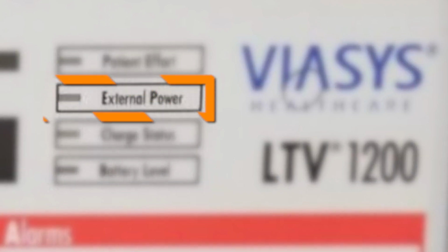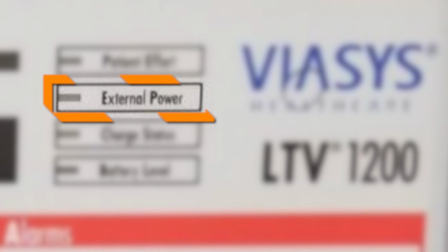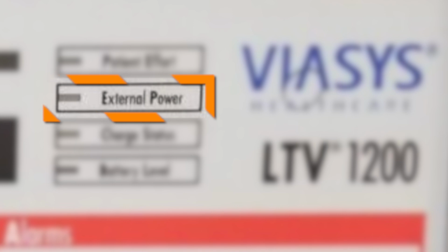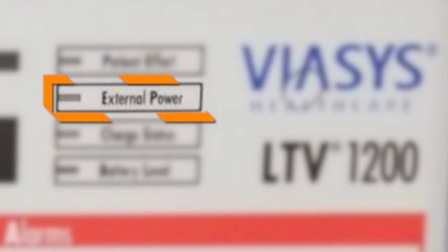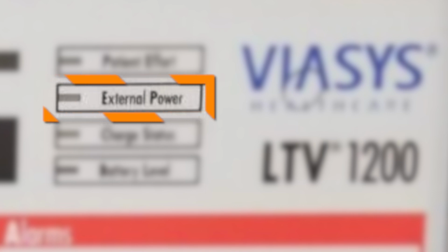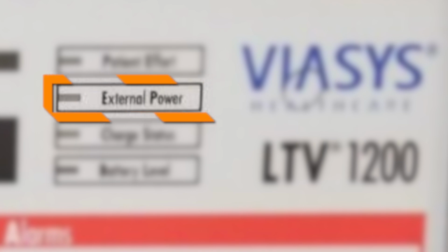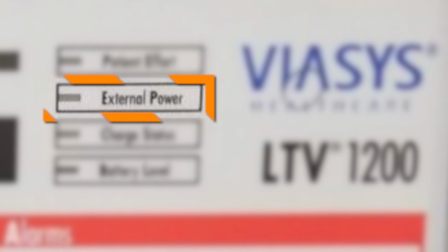The external power indicator shows the level of external power while the ventilator is operating from an external power source. When the ventilator is running from the internal battery, the external power indicator is off. When running from external power, the indicator shows the following levels. Green means the external power is acceptable. Amber means the external power is low. External power may be provided by connecting the ventilator to an external battery or to an external AC power source.